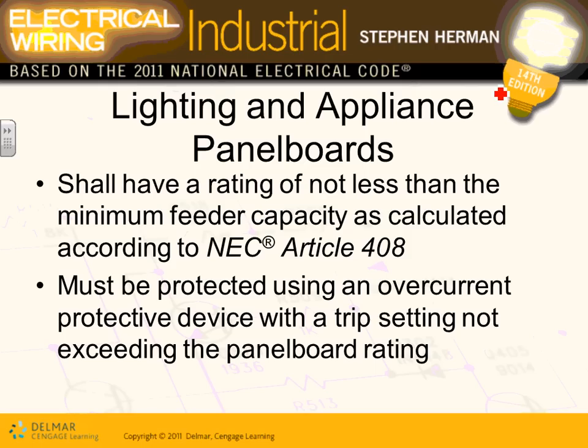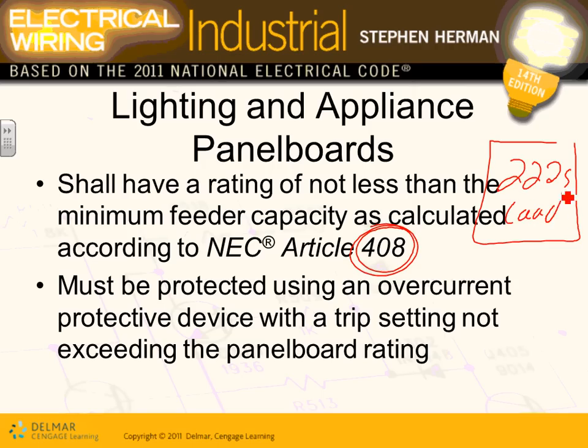Okay, a few things. We talked about this one article before, guys, and we'll be using it more often. Article 408 talks about the panels, and it says very simple. It says if you have a panel, and the panel is rated for 225 amp, it has to be rated to handle the load. You know, you can't have the load more than what the panel can handle, right? So your panel has to be sized based on Article 220 when you size your load. Karen, you guys have done this one for me last week when you sized your panels based on the load. That's what this is.